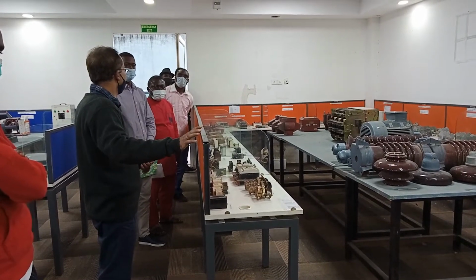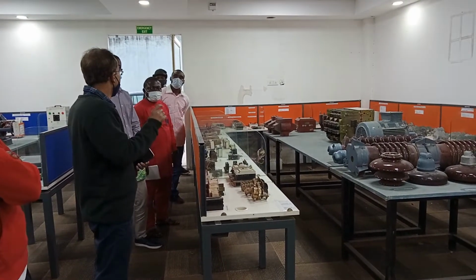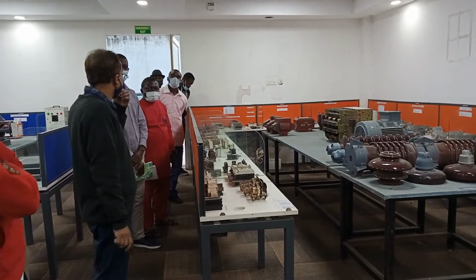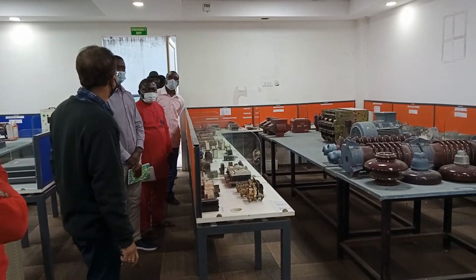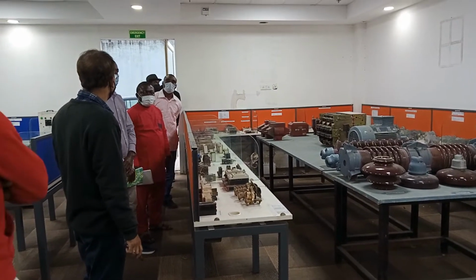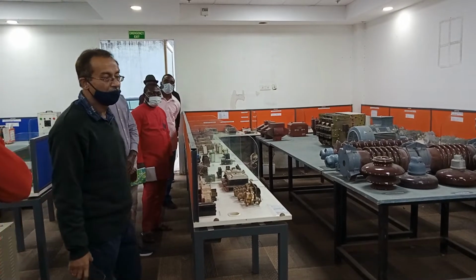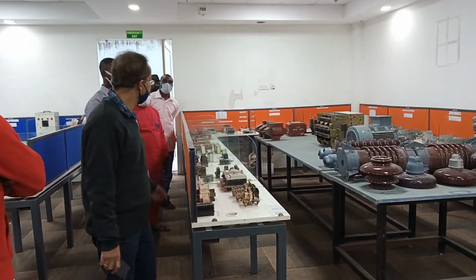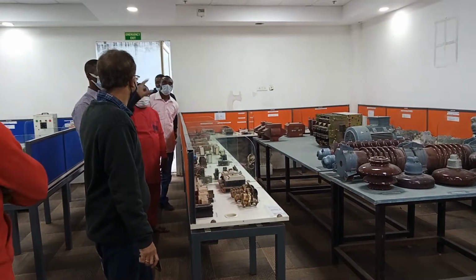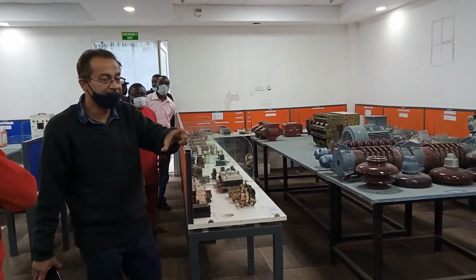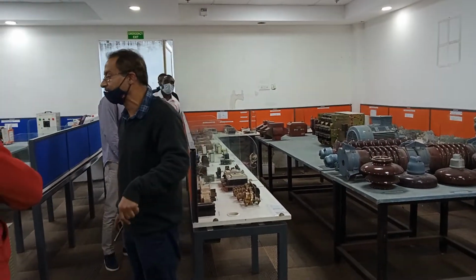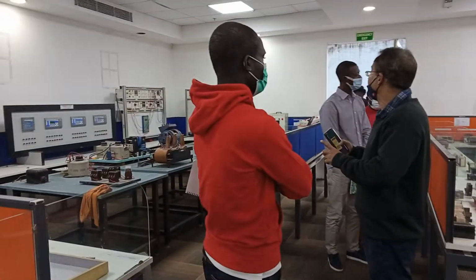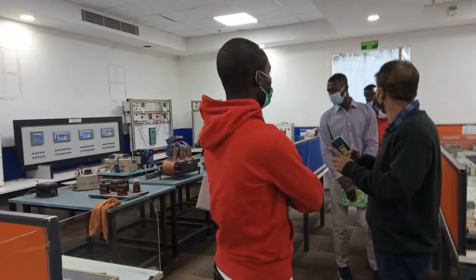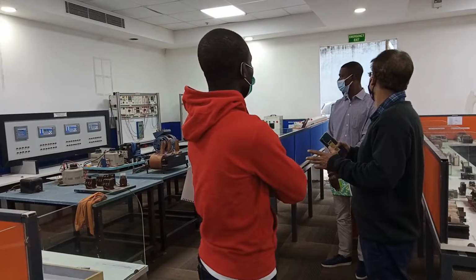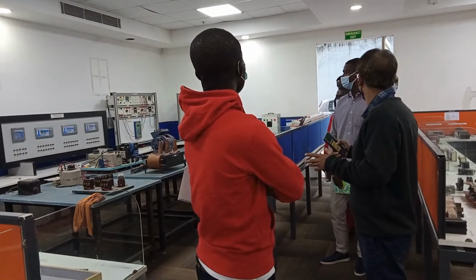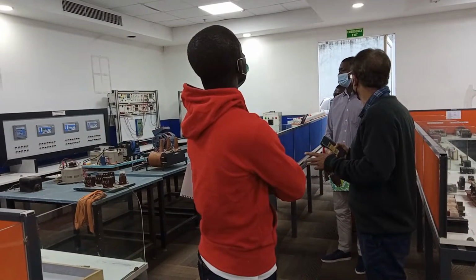And I hope you have seen after that there are certain types, like static type also, static relay, SPAM relay. Have you heard? So for motor protection, SPAM, and for feeder protection, SPAJ. So SPAM version, SPAJ version, and there are two types. One is feeder or line, sub-transmission line, another is transformers, and the third one is bus.